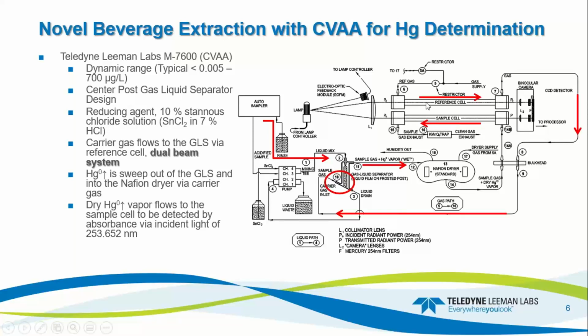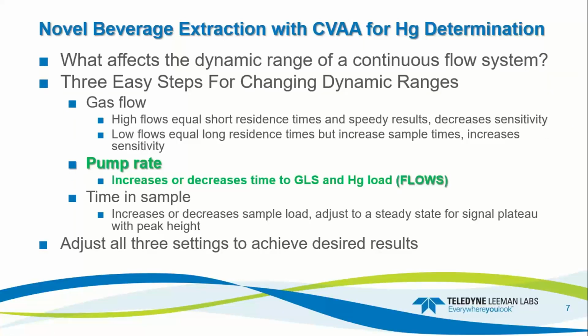So the carrier gas comes in through the reference cell, flows out of the reference cell, and goes over to the gas liquid separator. From there, the mercury's already been reduced to elemental mercury. It's going to be swept out, and it goes to the Nafion dryer and then to the sample cell for detection at the incident light of 253.652. So what affects the dynamic range of a continuous flow system?